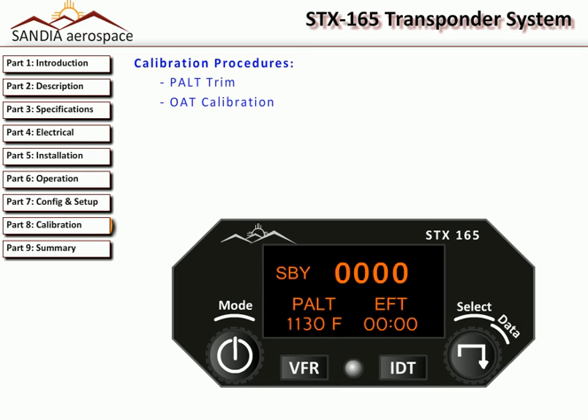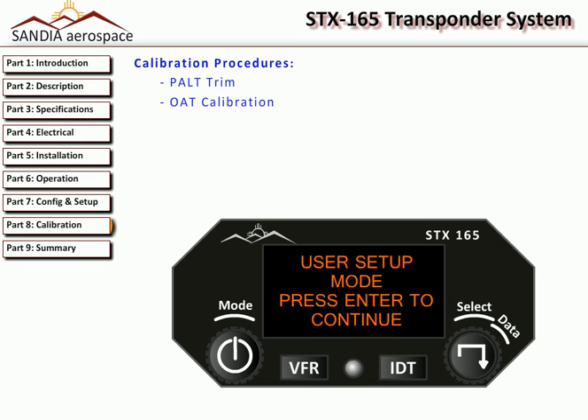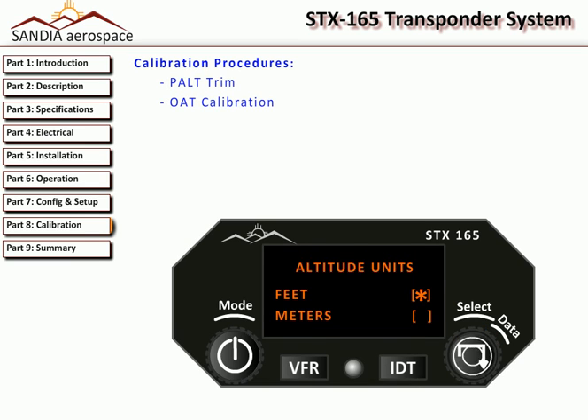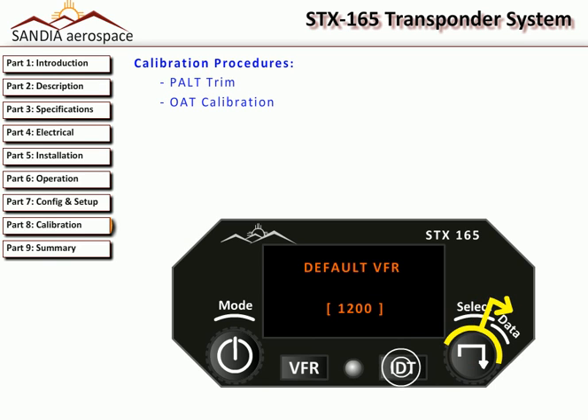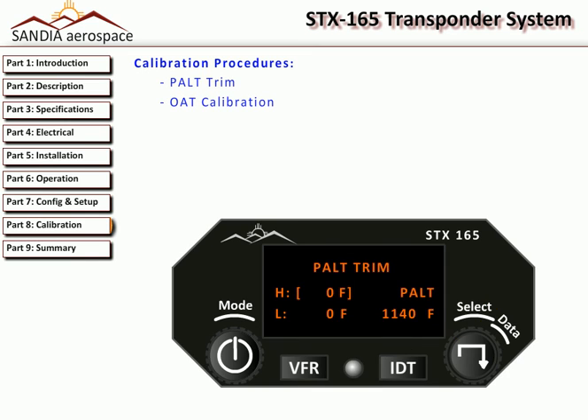Just to review how to get to the Install Setup mode, first enter the User Setup mode by holding the ident button and rotating the Select knob counterclockwise until it hits the hard stop. Continue holding the ident button and Select knob for 3 seconds until you see User Setup mode, then press the Enter button. In the User Setup mode, use the Data knob to scroll to the default VFR code page. Here you will again hold the ident button and rotate the Select knob clockwise until it hits the stop. Continue holding the ident button and Select knob for 3 seconds and you should see the pressure altitude trim page.